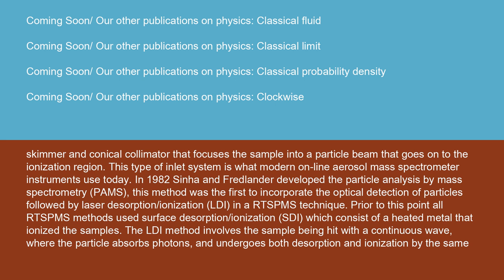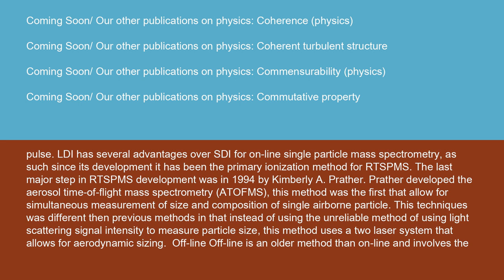In 1982, Sinha and Fred Lander developed the particle analysis by mass spectrometry (PAMS). This method was the first to incorporate the optical detection of particles followed by laser desorption/ionization (LDI) in an RTSPMS technique. Prior to this point, all RTSPMS methods used surface desorption/ionization (SDI), which consists of a heated metal that ionized the samples. The LDI method involves the sample being hit with a continuous wave where the particle absorbs photons and undergoes both desorption and ionization by the same pulse. LDI has several advantages over SDI for online single particle mass spectrometry, and since its development it has been the primary ionization method for RTSPMS.